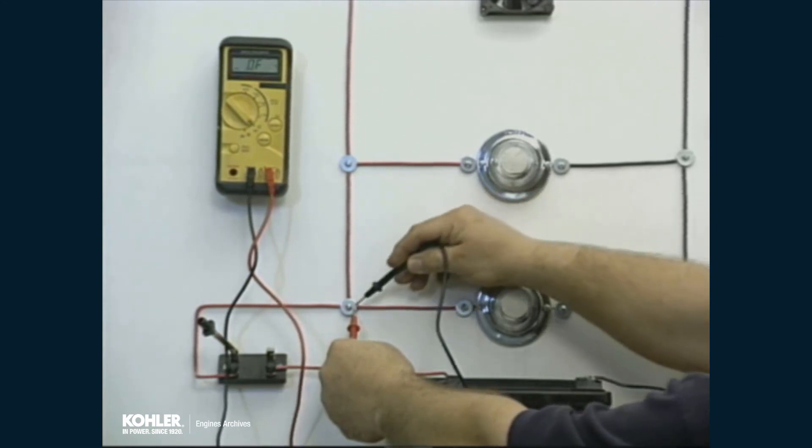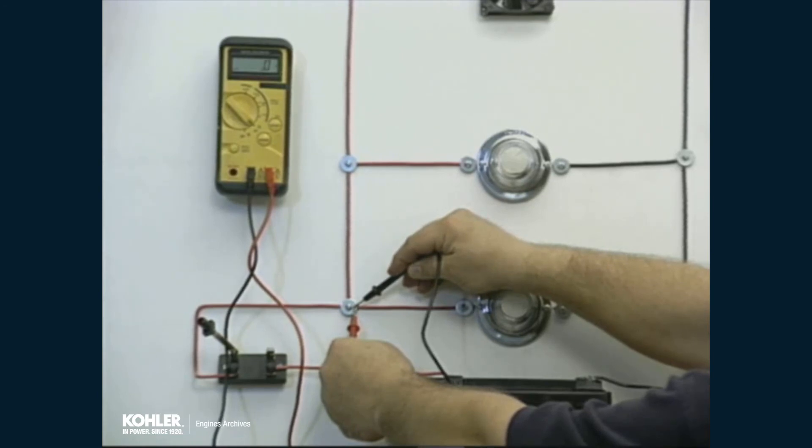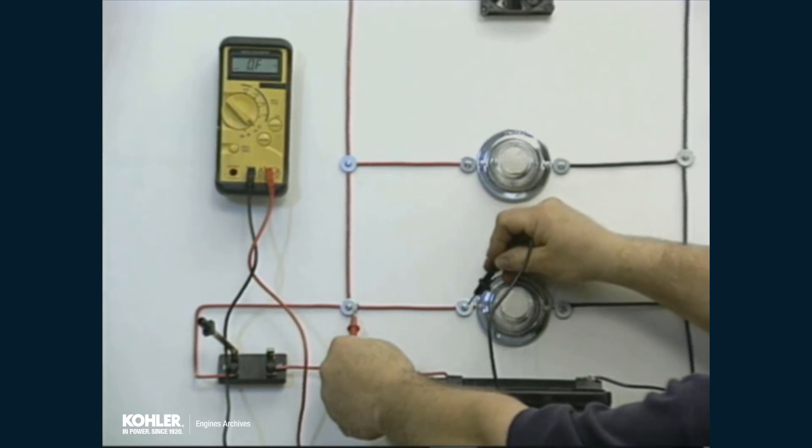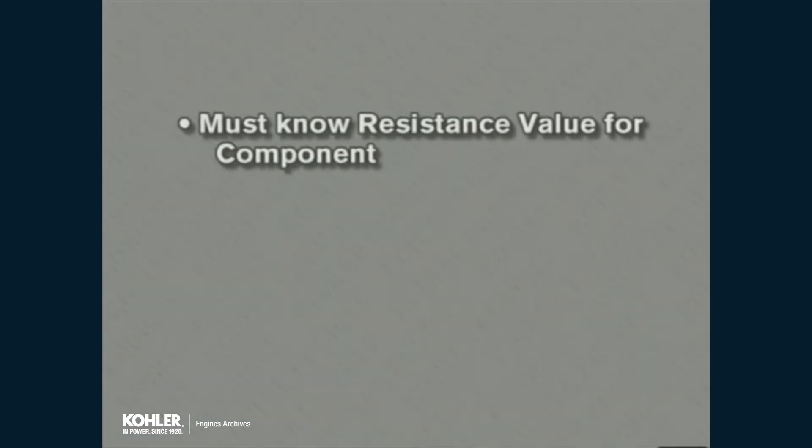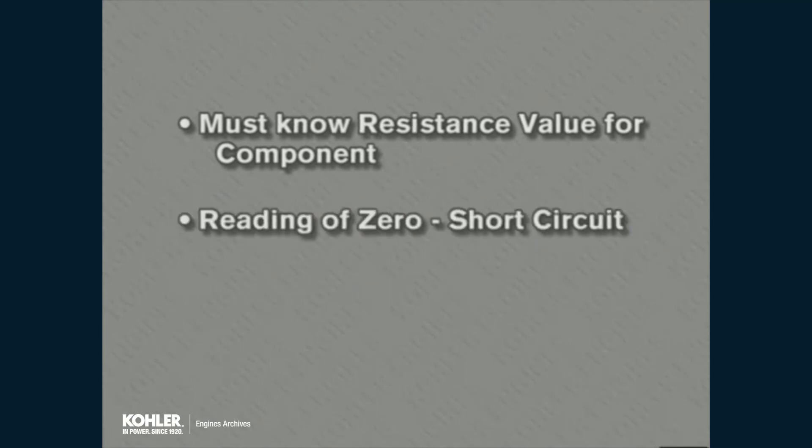If there are no working components or loads in the segment, resistance should be near zero. Higher resistance readings would indicate a continuity problem. If a component is being tested, you will need to know the resistance values for the component to make an accurate evaluation. Ohmmeter readings of zero ohms could indicate a short circuit, while very high readings could indicate an open circuit.